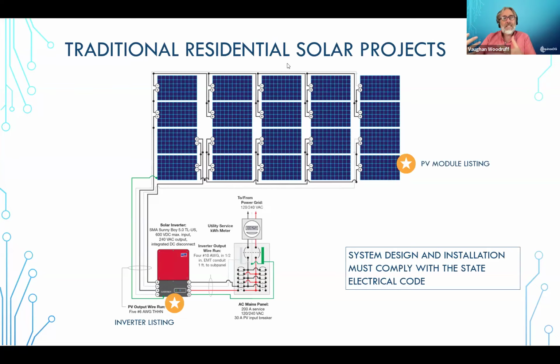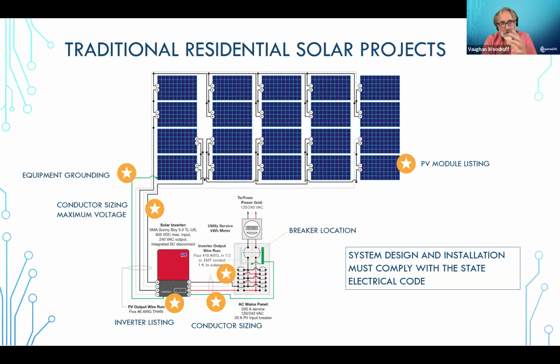By having these designs, you'll see this checks on a few things: that the module is listed, the inverter is listed, that the equipment is properly grounded, that the wires between the solar panels and the inverter are the right size, the ones between the inverter and the main panel are the right size, and that the panel itself is the right size. These are all the details involved.